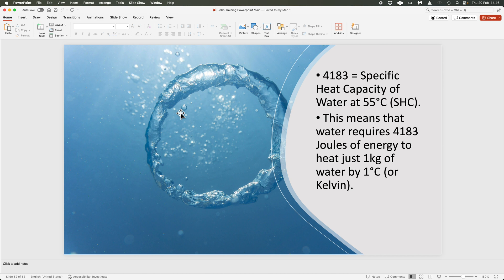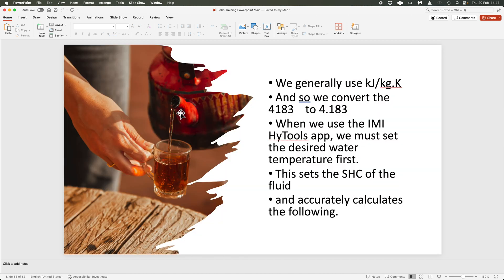So, 4183 joules of energy to heat just one kilogram of water by one degree Celsius or Kelvin — very important to understand. When working practically, we use kilojoules, so instead of 4183 joules — there are 1000 joules in a kilojoule — we convert that to 4.183. Because we're using the IMI HyTools app, I like to use 4.183, because as you change water temperature, specific heat capacity also changes: the higher the water temperature, the higher the specific heat capacity.